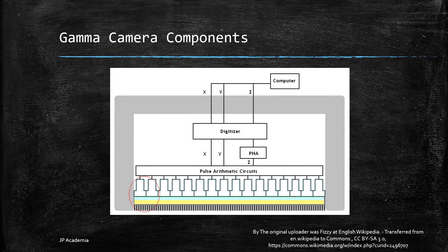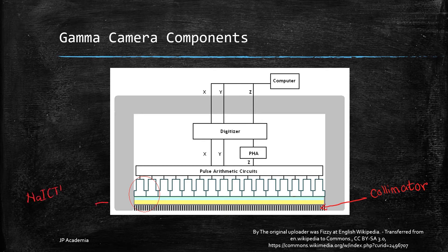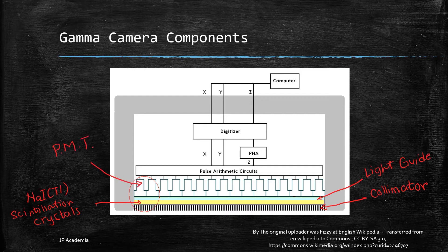Now, let's go to the main components of the gamma camera. We have the collimator, the sodium iodide doped with thallium scintillation crystals, the one in yellow here, then we have a light guide, followed by the PMTs or the photomultiplier tubes.